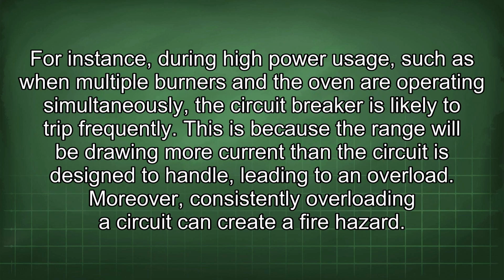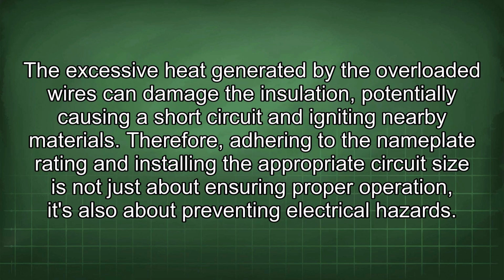For instance, during high power usage, such as when multiple burners and the oven are operating simultaneously, the circuit breaker is likely to trip frequently. This is because the range will be drawing more current than the circuit is designed to handle, leading to an overload. Moreover, consistently overloading a circuit can create a fire hazard. The excessive heat generated by the overloaded wires can damage the insulation, potentially causing a short circuit and igniting nearby materials. Therefore, adhering to the nameplate rating and installing the appropriate circuit size is not just about ensuring proper operation, it's also about preventing electrical hazards.